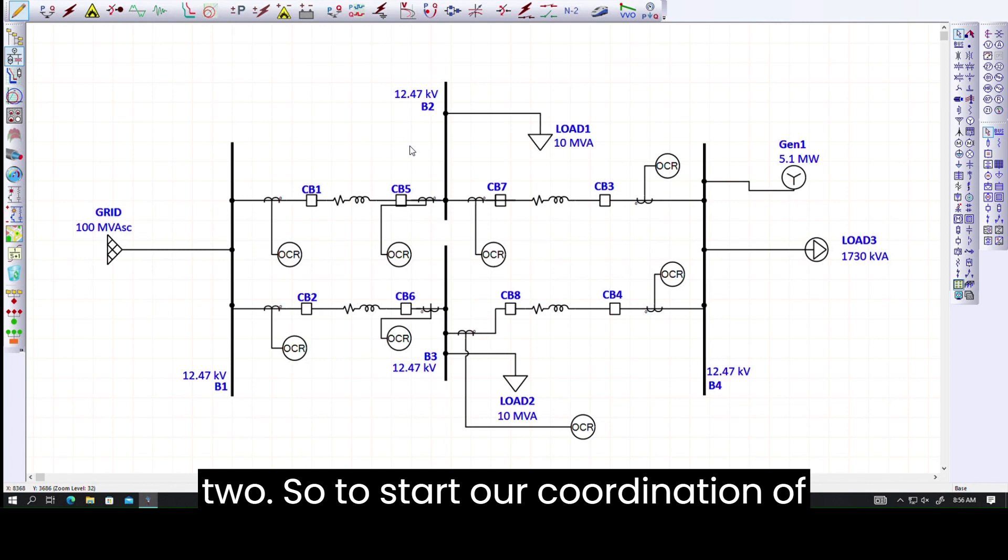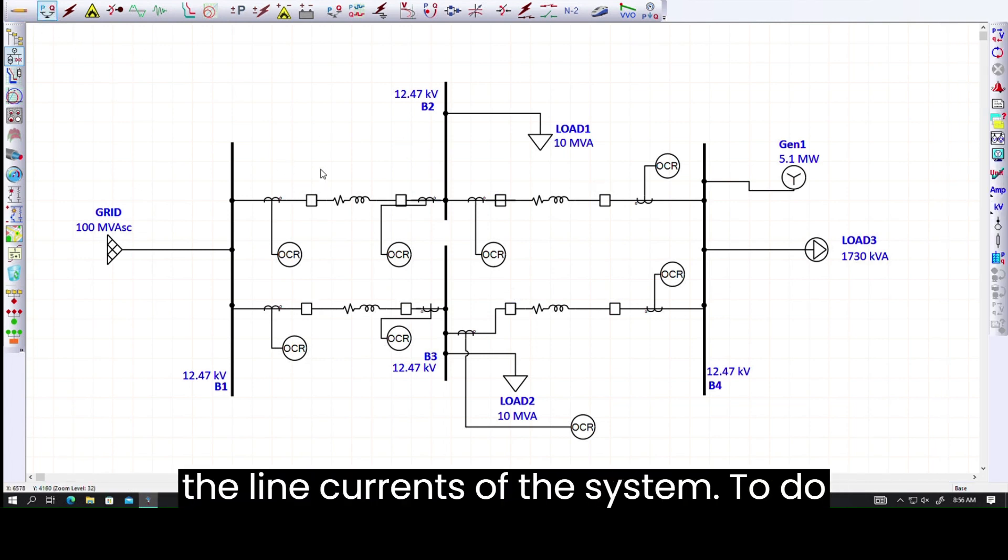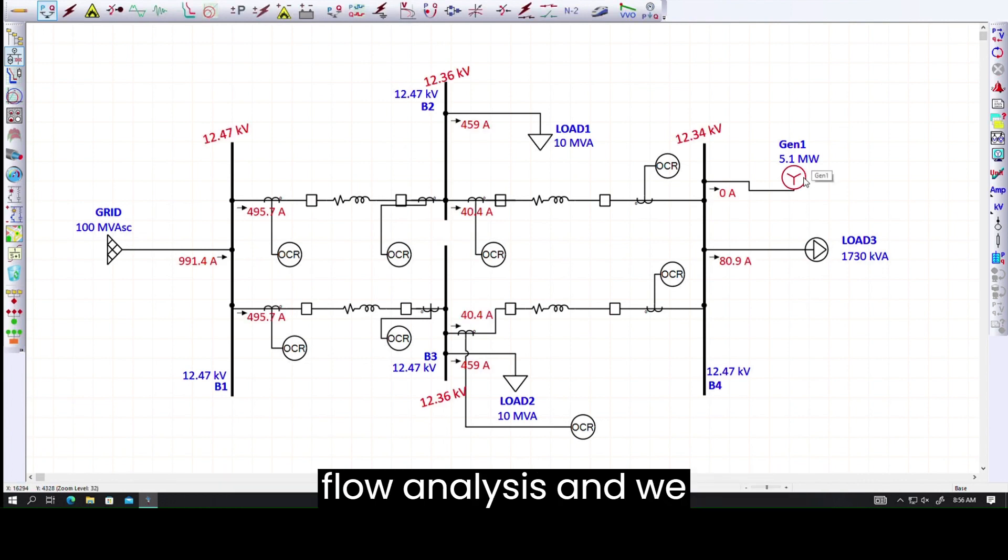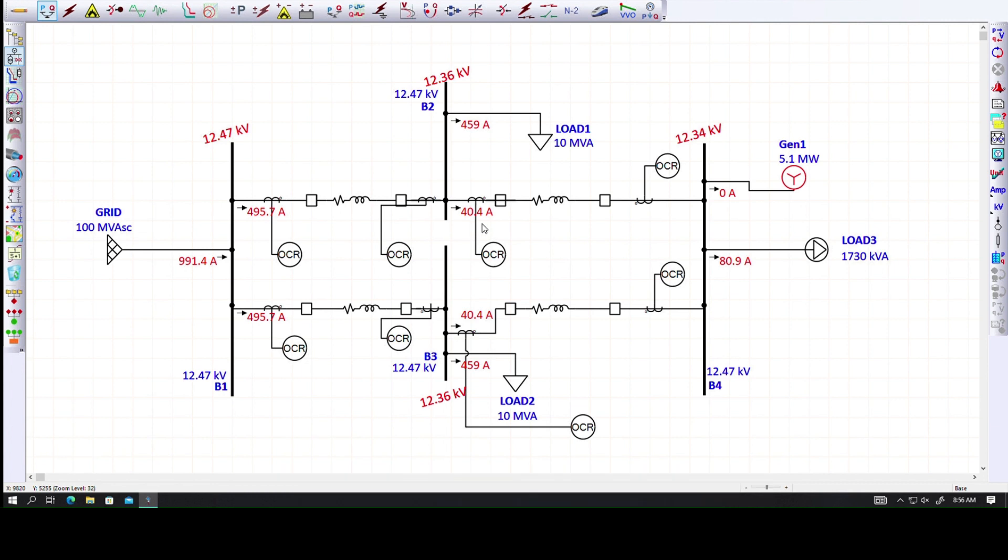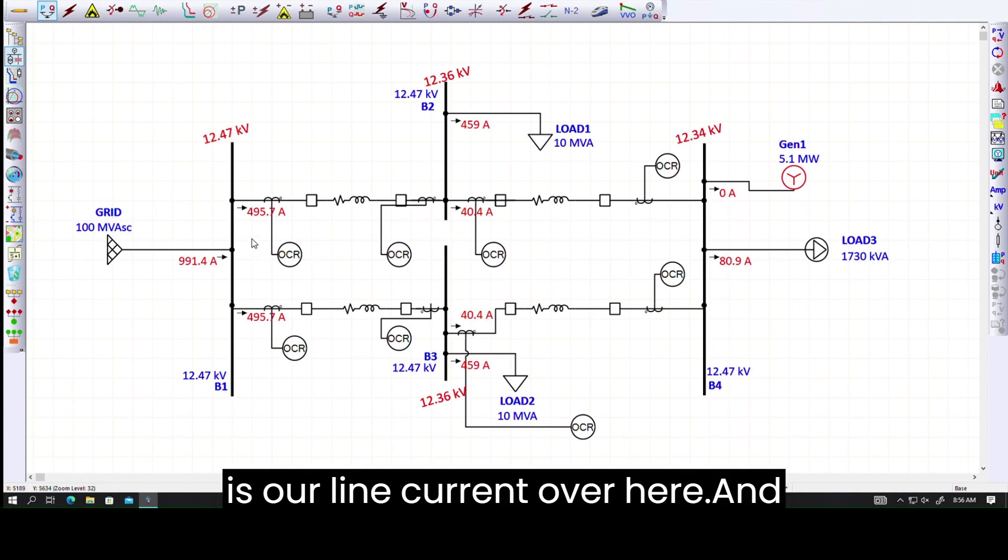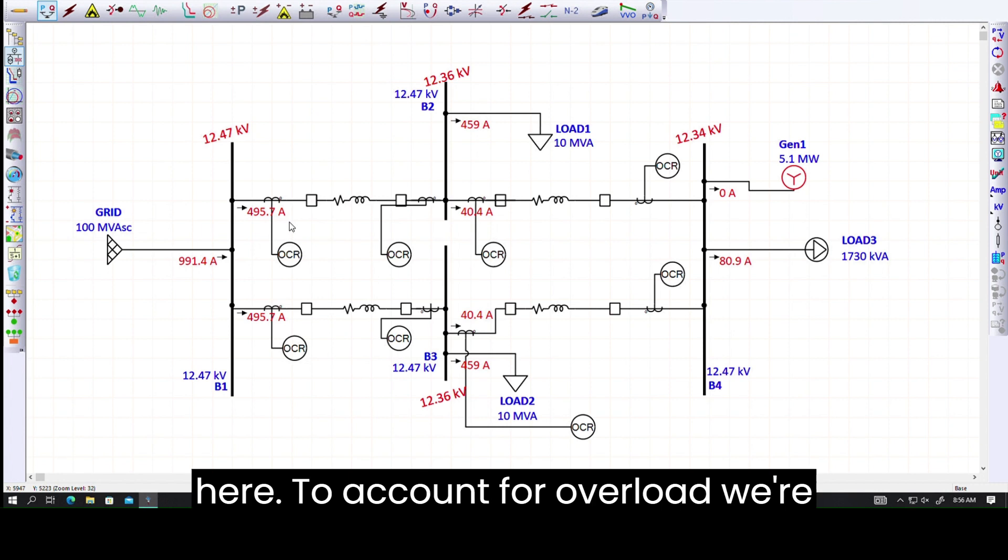To start our coordination of this loop system, we need to figure out the line currents of the system. To do that, we're going to run a load flow analysis and we determine that 40.4 amps is our line current over here and 495.7 amps is the line current over here.